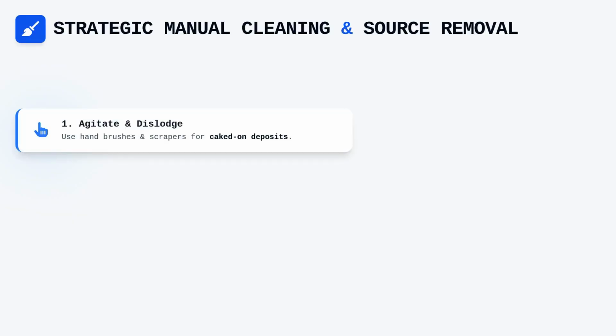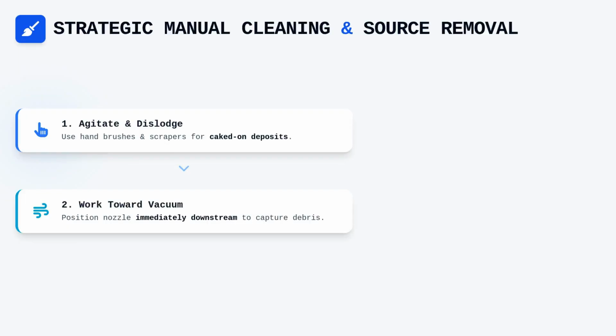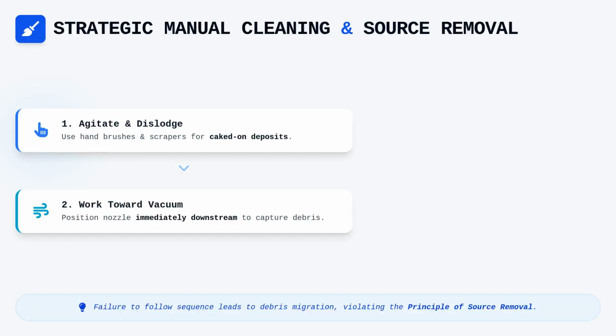Strategic use of manual tools like hand brushes and plastic scrapers is often mandatory when dealing with stubborn, caked-on deposits that suction alone cannot dislodge. When using these tools, you must always employ a work toward the vacuum methodology, where you agitate the debris while ensuring the vacuum nozzle is positioned immediately downstream or adjacent to the cleaning action to capture the loosened material. Neglecting this sequence often results in the migration of dust into areas you have already cleared or deeper into the system, which directly violates the principle of source removal.